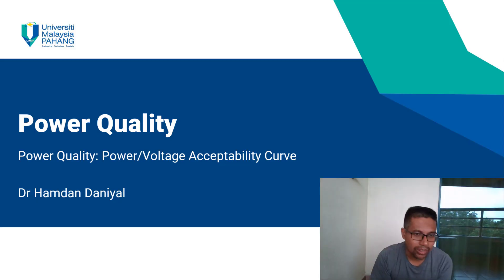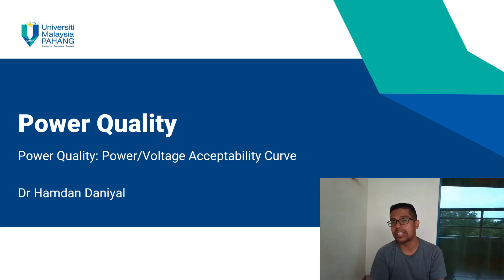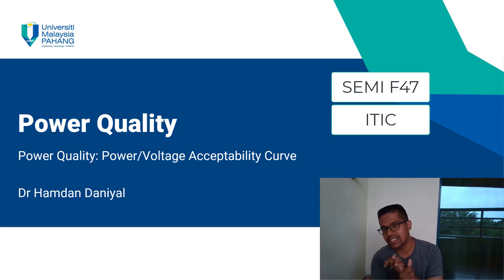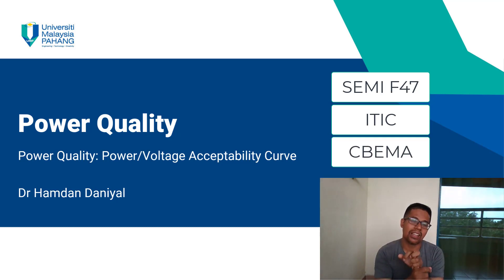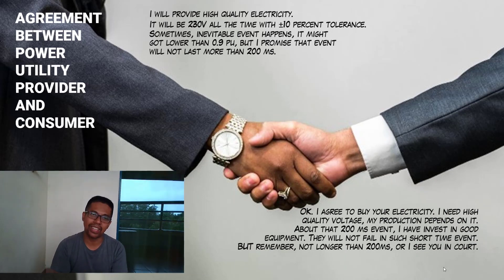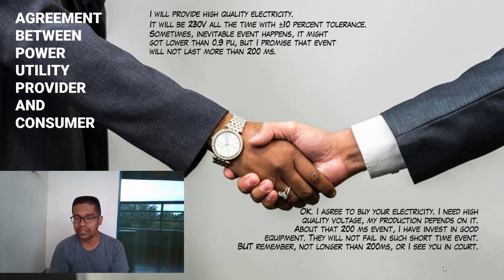Today we will talk about power quality, specifically the power acceptability curve or voltage acceptability curve. There are several acceptability curves available according to different standards: SEMI F47, ITIC, and the old CBEMA standard. All three have different curves, and this curve represents the agreement between the power provider and the power consumer.